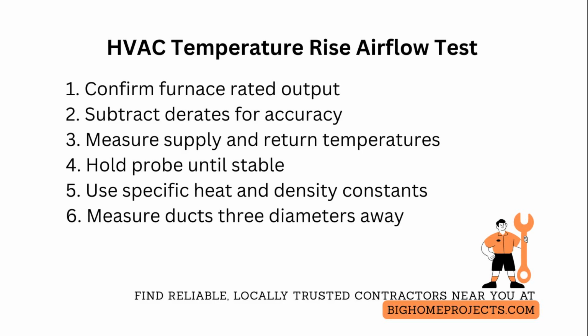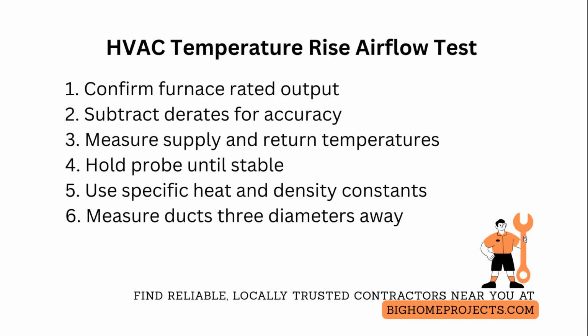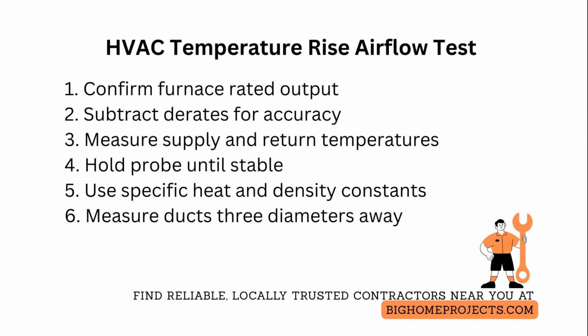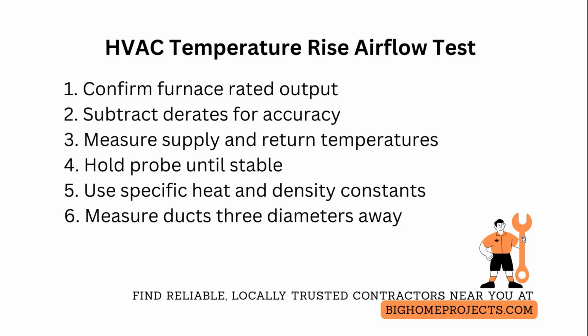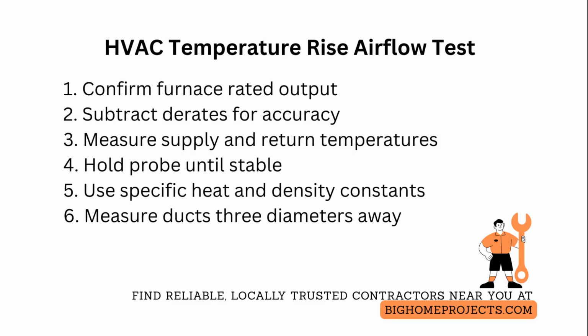When measuring, ensure ducts are full of mixed air. Measure return air at least 3 duct diameters upstream of filters or obstructions, and supply at least 3 diameters downstream of bends or takeoffs to avoid skewed readings. Account for fan-off, heat soak, and combustion influence by recording multiple readings after steady state for a minimum of 5 minutes and averaging them. Correct for high altitude by adjusting air density if you are above 1,500 feet elevation.